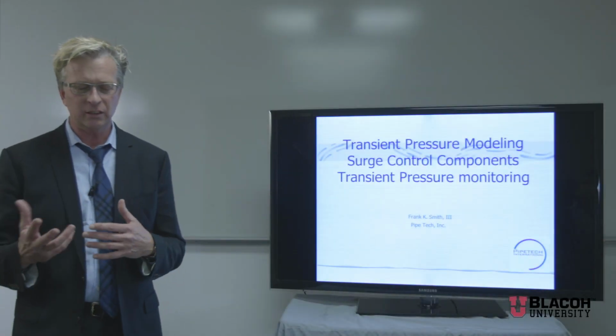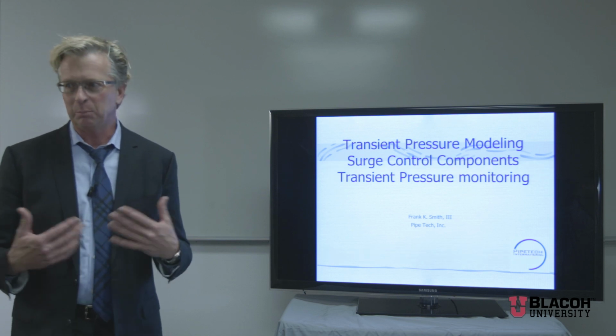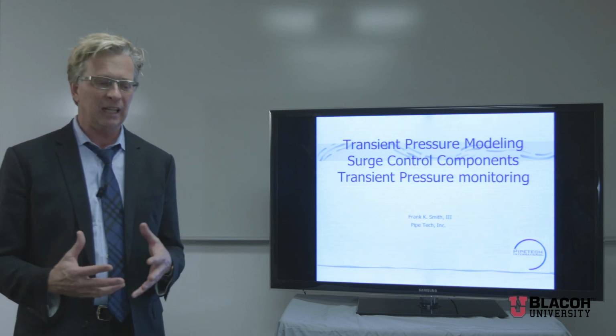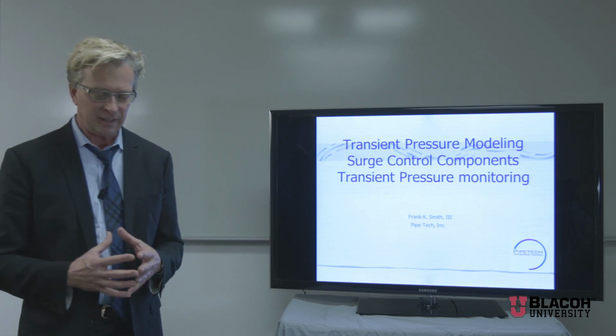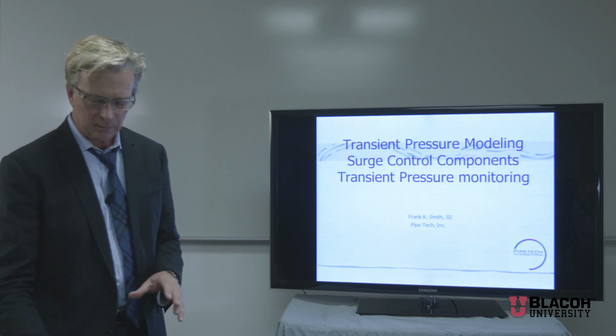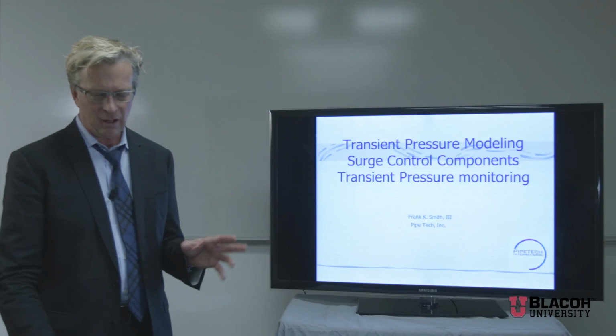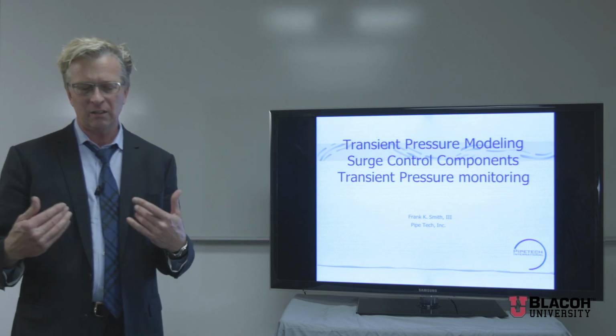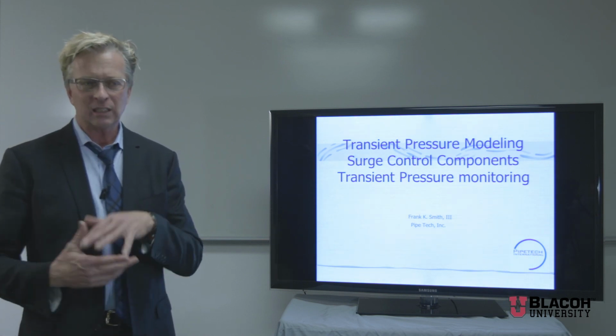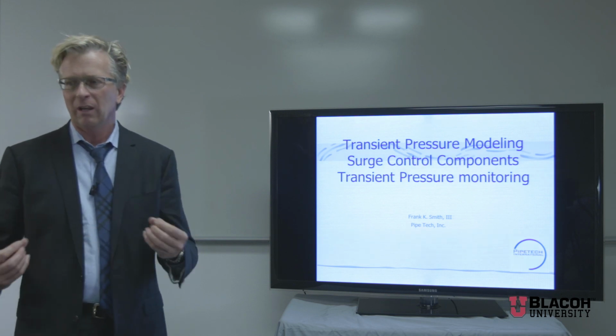About transient surge modeling, then there's actually proof of design in the field: gathering data and recording that transient event. In a lot of cases, when I ask customers, oh, you have a pressure transmitter on the system hooked up to SCADA, give me that data in a file so I can look at it. And you end up with a huge data file, and it's very difficult to find the transient event that occurred. Pipe Tech International developed software that has a trigger that they got a patent on, that when you go outside a given pressure envelope, it'll record at a faster rate.